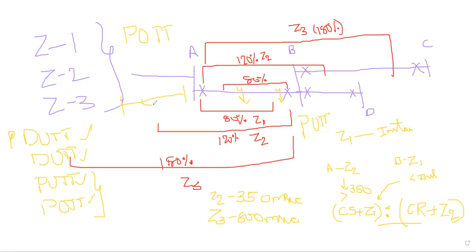Maybe due to the ground arc fault resistance, both relays are showing zone 2 only. Zone 2, zone 2. So if both relays are in zone 2, with carrier send and carrier receive, it resembles the POTT scheme, permissive overreach transfer scheme. Why is it falling in zone 2 on both? Because of the arc fault resistance, which is creating an impact on the impedances.